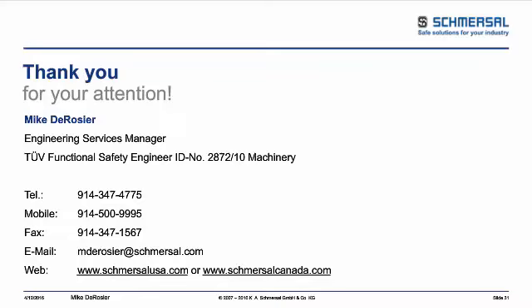So that becomes, and like you said, it becomes a gray area. It depends on the use, and under normal operating principles, who's allowed to throw disconnects on a machine and cycle power to that. Ultimately, it does come down to a training issue, that when you have that potential situation, if you open and close a door and the machine doesn't restart, that's your flag to call maintenance, because there's something wrong with the safety circuit. The safety circuit actually did its job. It stopped the machine, allowed you to do what you needed to do, but prevented you from restarting because of the fault that's in the system.